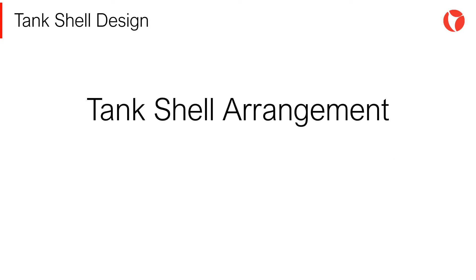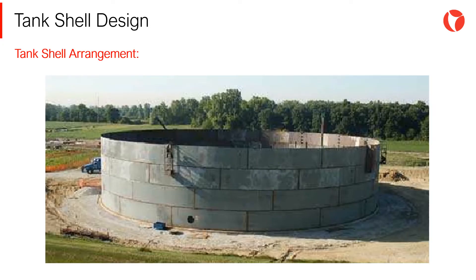The shell is the largest and most critical component of storage tanks, representing approximately 60% of the total material used. The tank shell, or tank wall, is built from standard plates with standard width and length according to the origin of the material. The layout of the plates follows an arrangement where vertical welded joints are out of phase, rotated at a certain angle in order to avoid stress concentration.